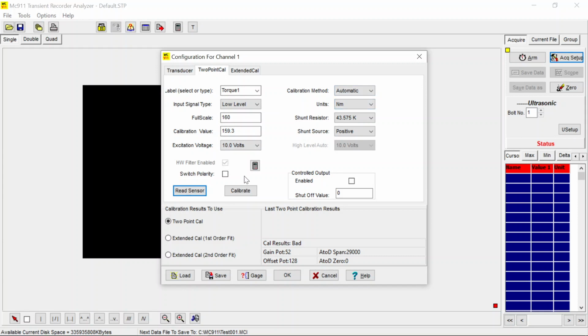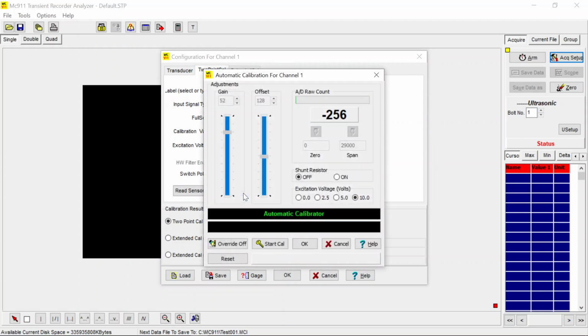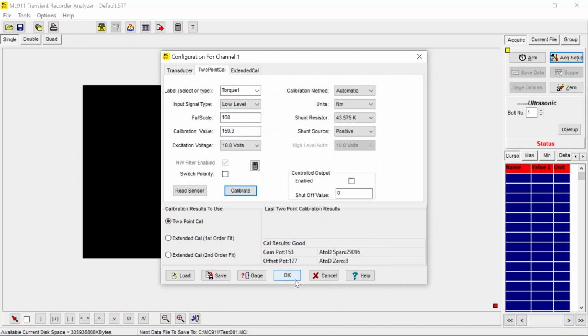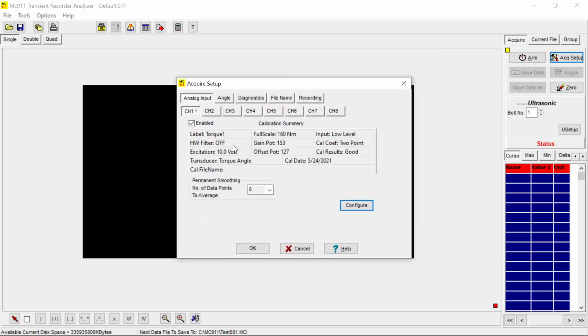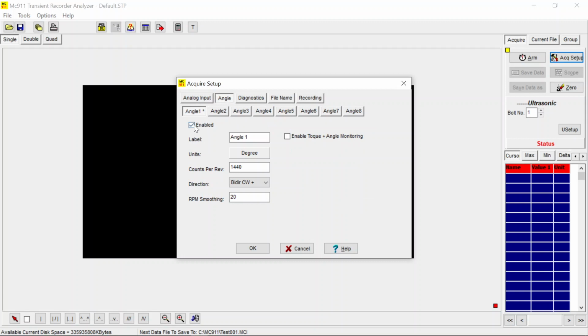In our fixture, we calibrate this, start cal. It's calibrating torque with MC950. So this needs to be close to 0. So click OK. Let's make sure our angle is also enabled and our count per revolution is correct. In this case, 1440 for this transducer.